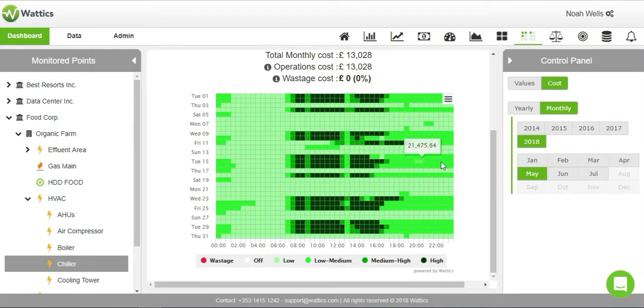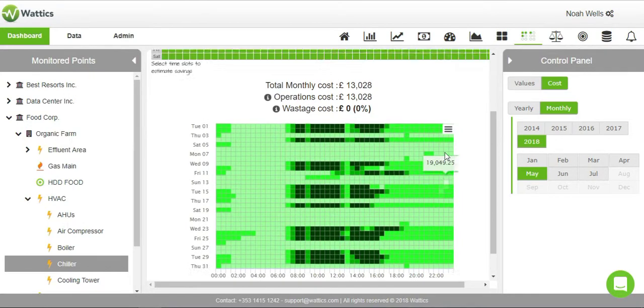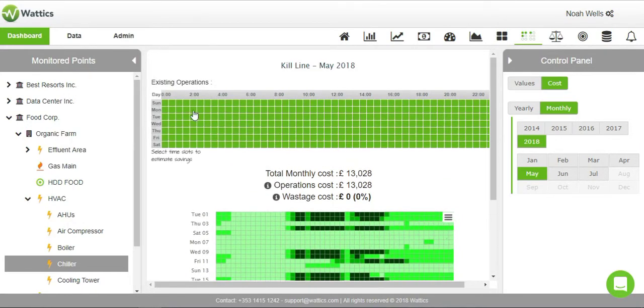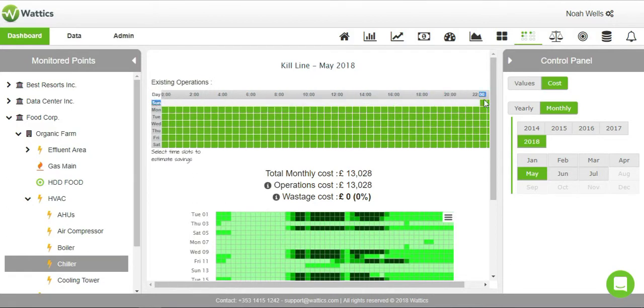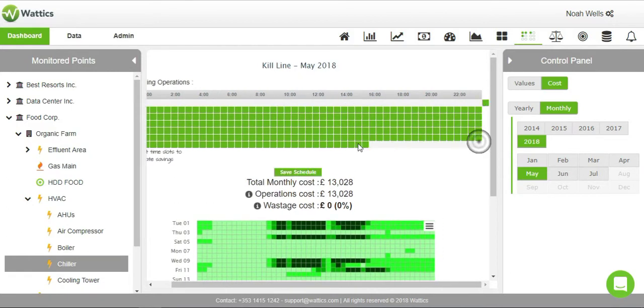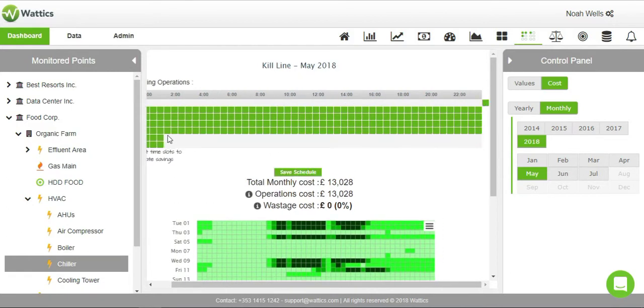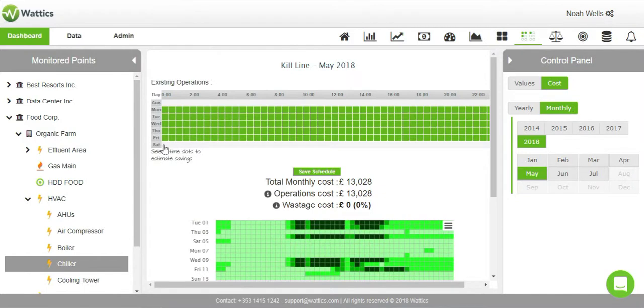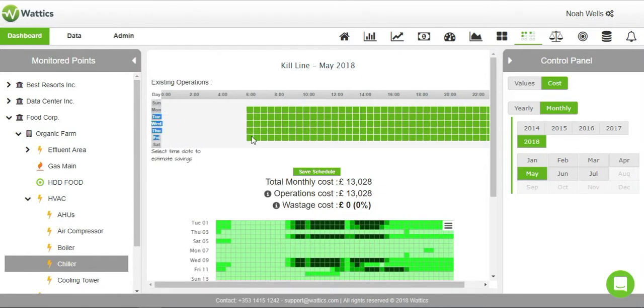Using the same appliance from the activity maps, the figure is replicated below. If we choose to turn off the chiller all day Saturday and Sunday, and every night from 8 to 6, we can deselect the green boxes in the existing operation schedule and the system will recalculate how much energy or cost you would have saved.